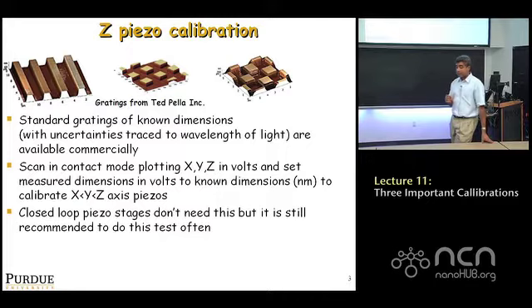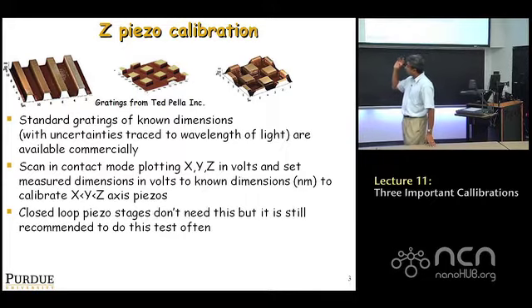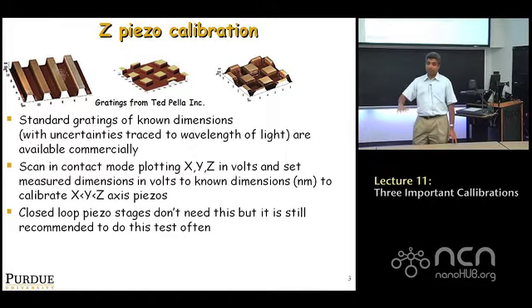It's very important because they might say this calibration standard is 10 nanometers high, but in reality, it's not 10 nanometers high. It's going to be 10 plus or minus 1 with a probability of 90%, right? So the idea then is that you take this known dimension and scan in contact mode, right? Now remember, when you first scan this image in contact mode, your height is going to be in volts. It's the volts applied to the base of the piezo to keep the deflection constant. So you're going to get volts versus volts applied to the X piezo, volts applied to the Y piezo, right? That's the basic image. Somehow the AFM system is converting volts, X, Y, Z into nanometers, nanometers, nanometers.